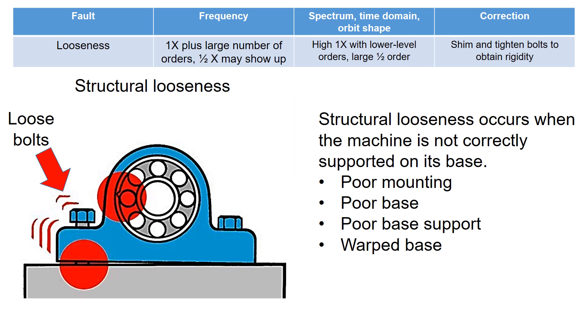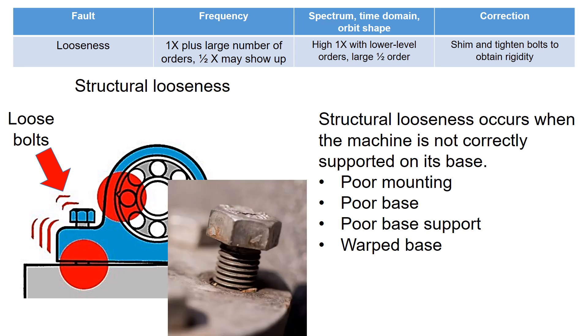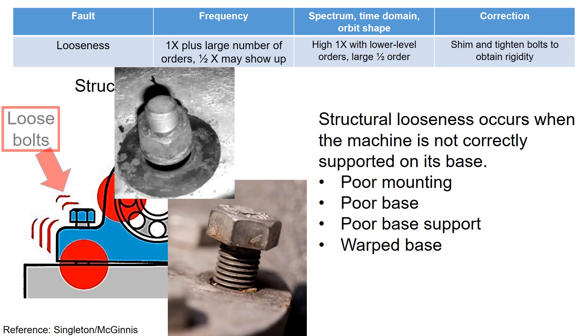Structural looseness manifests when the machine lacks proper support in its base. Poor mounting, poor base support, and distorted base can contribute to structural looseness. Of course, the primary cause of major issues often stems from loose bolts.